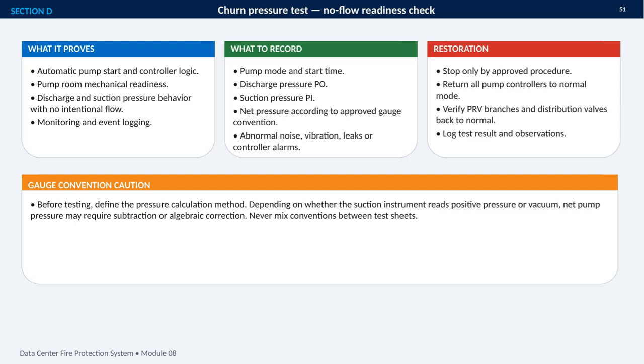This slide defines a no-flow readiness check for the data center fire protection system, focused on churn pressure and the pump's response without intentional discharge. It proves several things at once: that the pump starts automatically, the controller logic works, the pump room is mechanically ready, pressure behaves as expected, and events are monitored and logged.